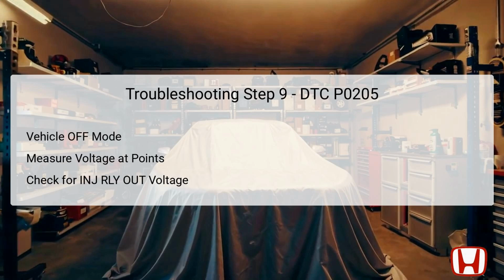Step 9 entails returning to off mode and disconnecting the injector control module connector D. You will then jump specific terminals between the injector relay 4P socket and assess the voltage at designated points. This step focuses on the INJ-RLY out/IGEDU1 line, ensuring that sufficient voltage reaches the injector control module. If any voltage is present, proceed to step 10. Otherwise, you must repair the wiring path to eliminate any open in the INJ-RLY out/IGEDU1 wire.